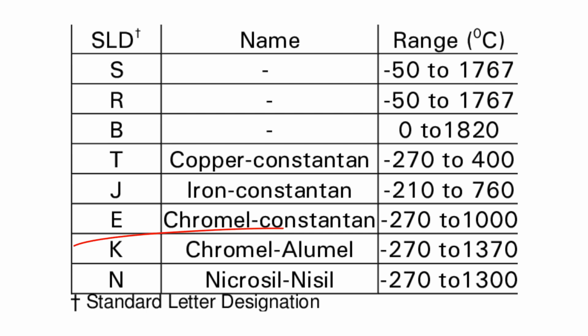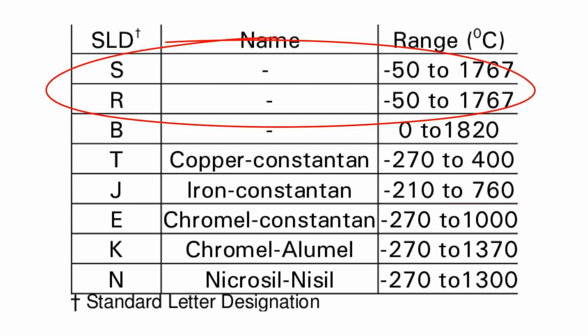For example, type K thermocouples are made of chromel and alumel alloys and are the most common for general industrial use. The temperature range is between negative 270 degrees Celsius up to 1370 degrees Celsius. For type E, we have chromel and constantan. The typical range is between negative 270 degrees Celsius up to 1000 degrees Celsius. Type J, made of iron and constantan, works well for lower temperatures, while platinum alloys are suited for very high temperature applications, such as furnaces and glass manufacturing.